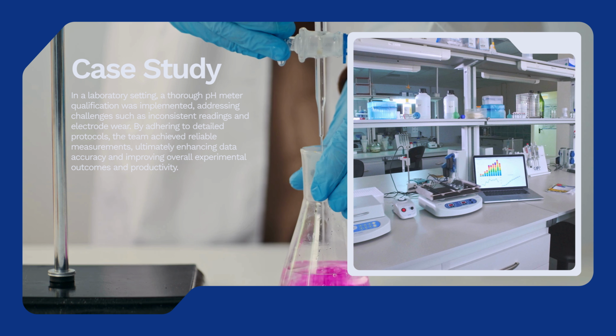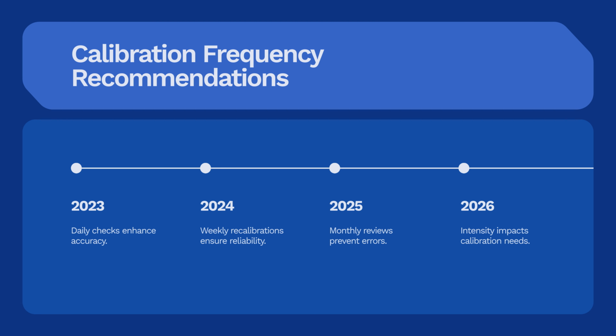Calibration needs will naturally change over time based on the frequency of use. While daily checks significantly enhance day-to-day accuracy, weekly recalibrations are often sufficient to ensure long-term reliability. By looking ahead to 2025, regular monthly reviews can help prevent cumulative errors, though the specific intensity of your lab's use will always dictate your needs.